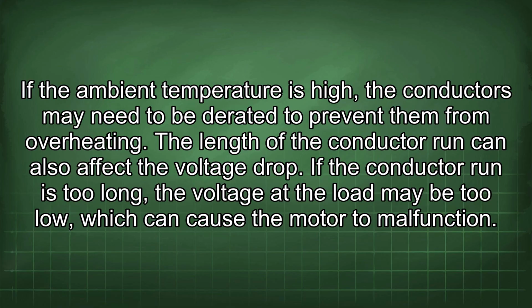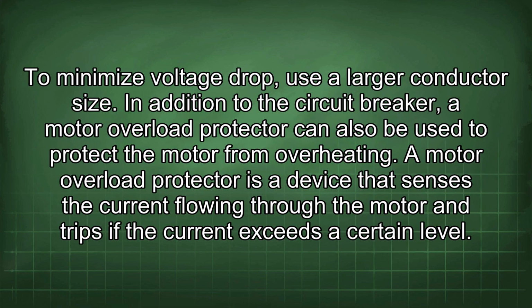The length of the conductor run can also affect the voltage drop. If the conductor run is too long, the voltage at the load may be too low, which can cause the motor to malfunction. To minimize voltage drop, use a larger conductor size.